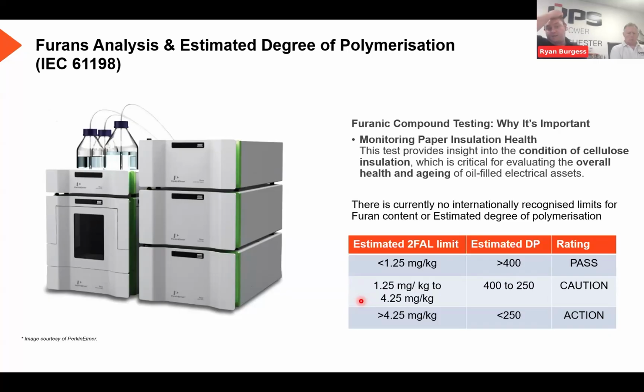So here at VPS, we use a model known as Chendong, and we use the analyte 2-furfural, also known as 2-FAL, to calculate that aging process. As you can see at the bottom here, we have a list of numbers. This isn't a specification. There isn't an internationally recognized specification out there. I'll call it a specification, but it is based on guidelines from multiple sources around the world. As you can see, anything with a DP of over 400 would be a pass, indicating that the asset is still in good health. But depending on whereabouts on that range it is, we can determine how well it is.